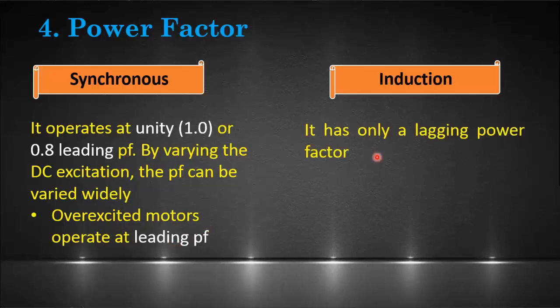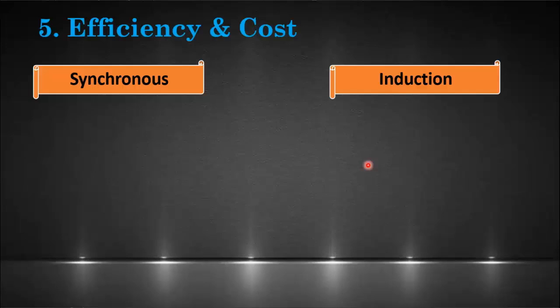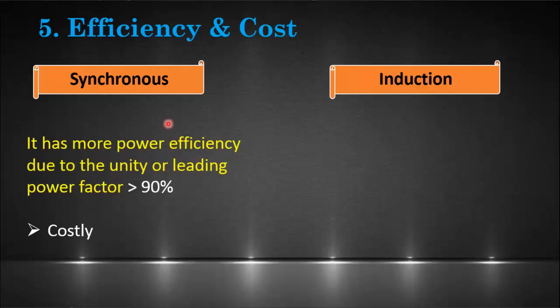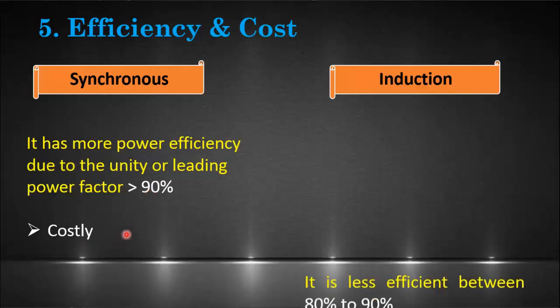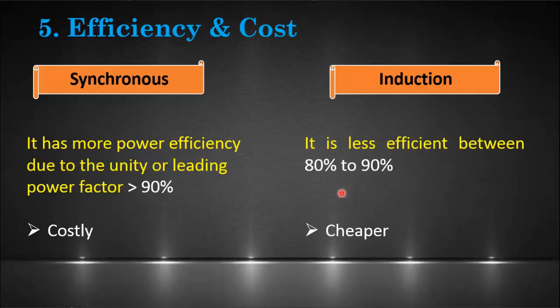The final difference is based on efficiency and cost. The synchronous motor is more power-efficient due to its leading or unity power factor, with efficiency normally above 90%. Synchronous motors are more costly compared to induction motors. Induction motors are considered less efficient, with efficiency ranging between 80% and 90%, but they are cheaper than synchronous motors.